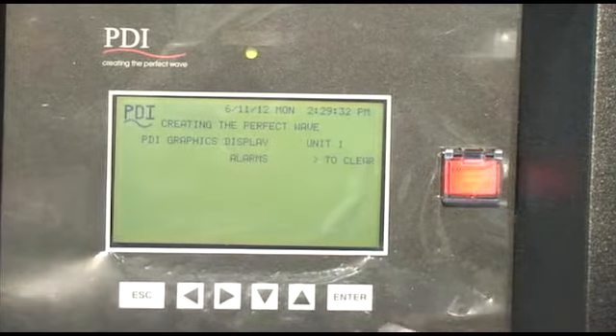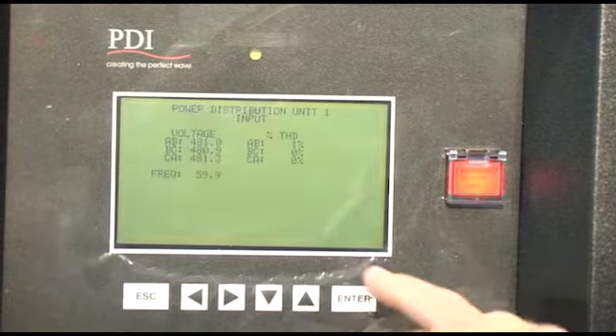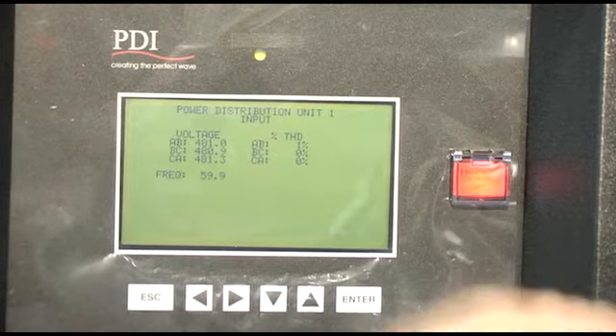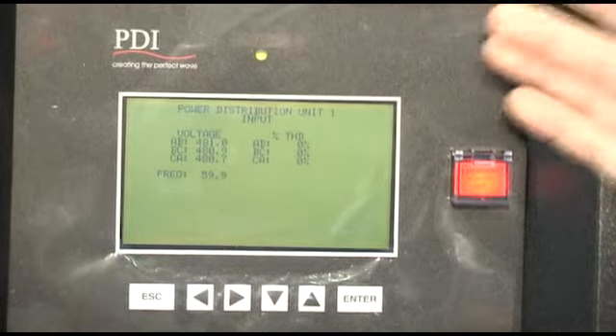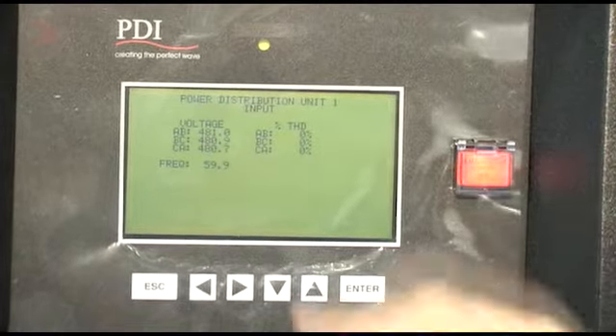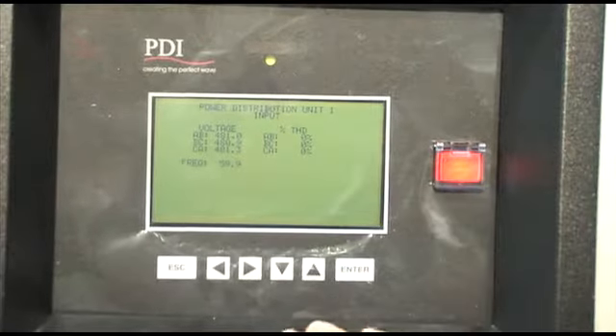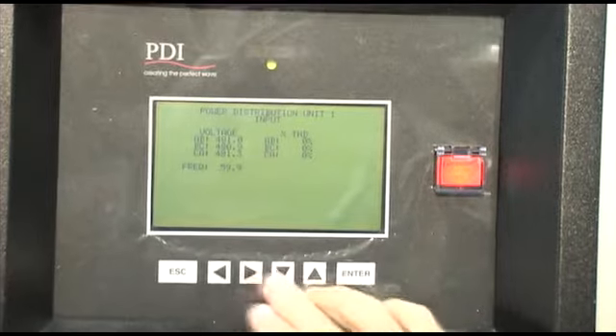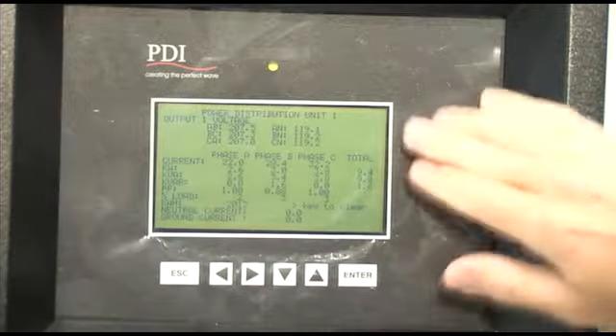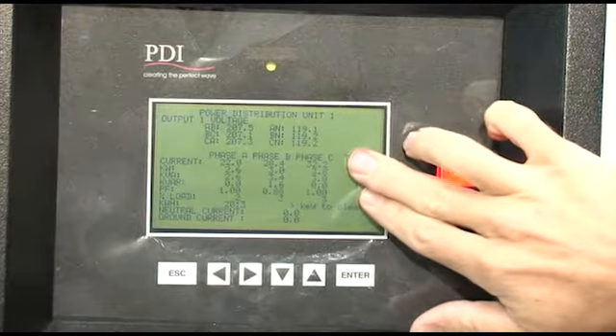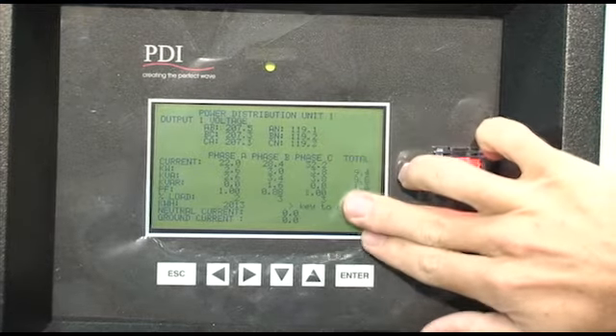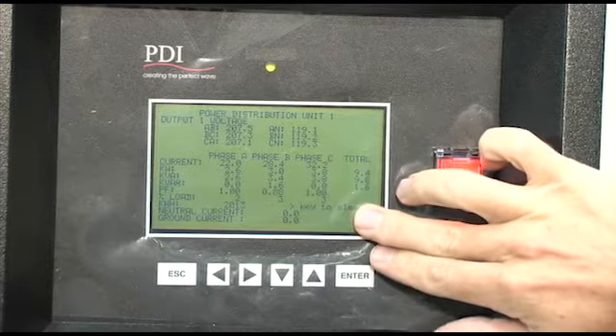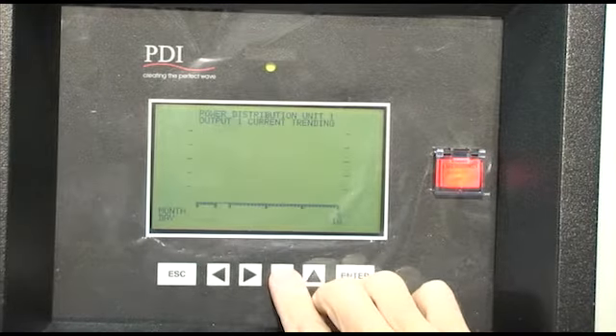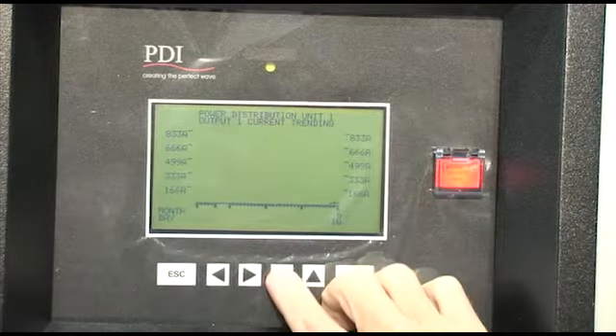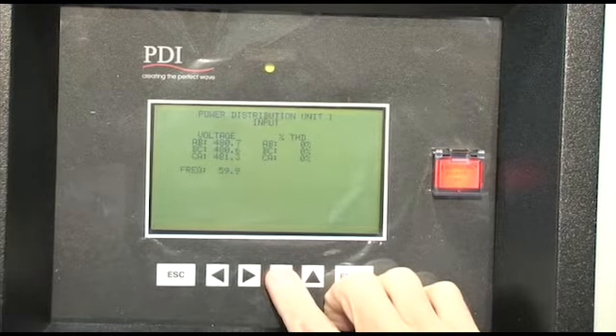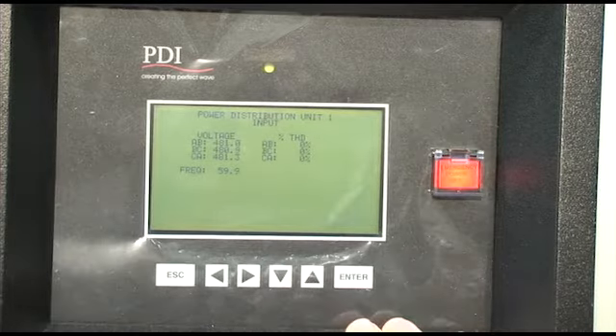So also going back to the display, when you press the enter button, it goes from the alarm record to the voltages and the currents in this case. It's going to have voltages for the input of this entire unit, and then when you scroll down it'll have the voltages of the output, and then it'll have kW, kVA, kilowatt hours, neutral current, and things of that nature. You continue to scroll down and it'll have a current read for the output of this unit, and then it's back to the voltage screen.